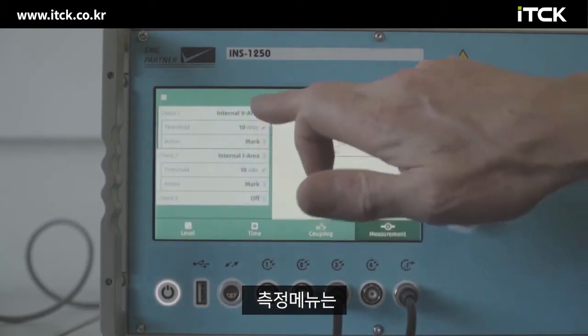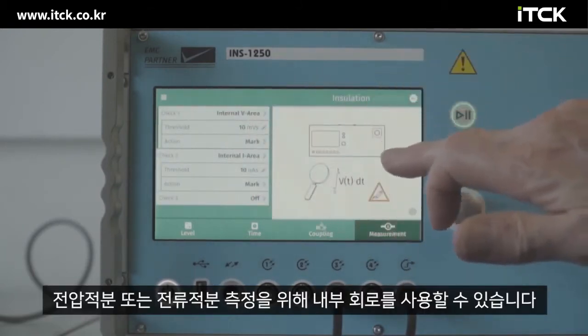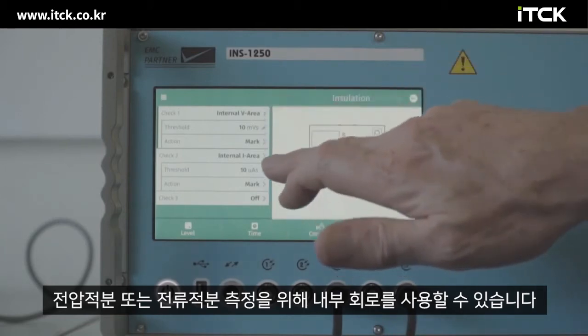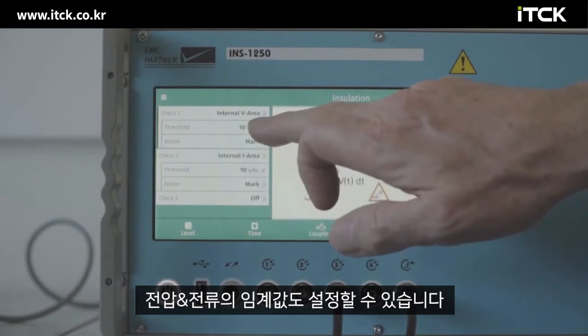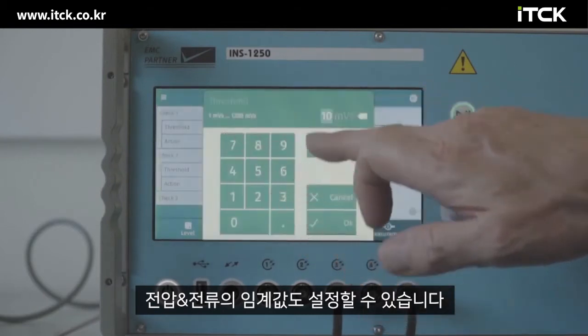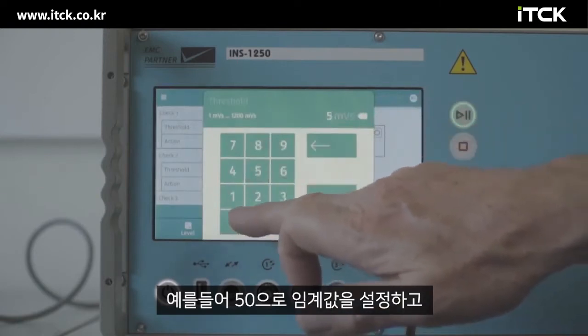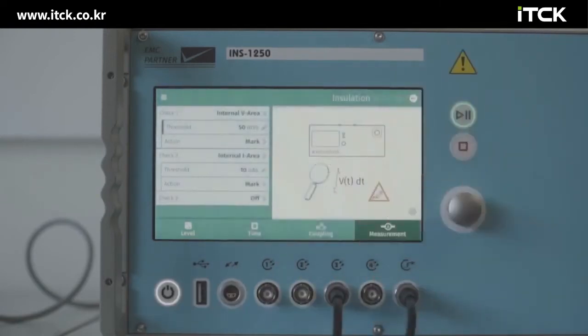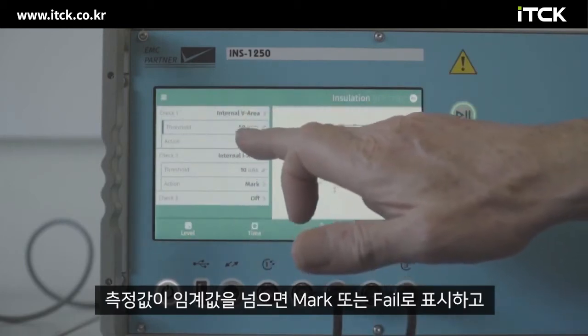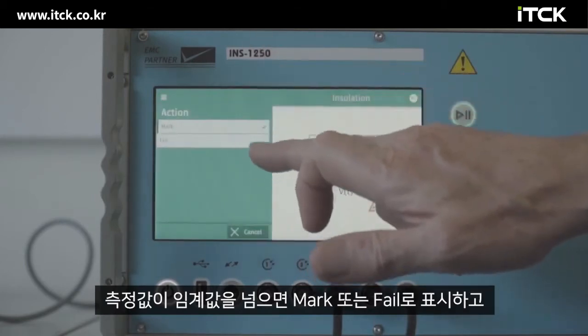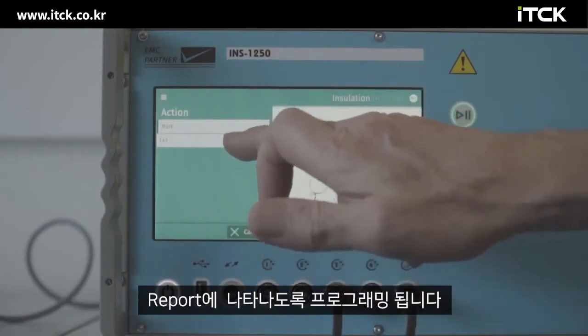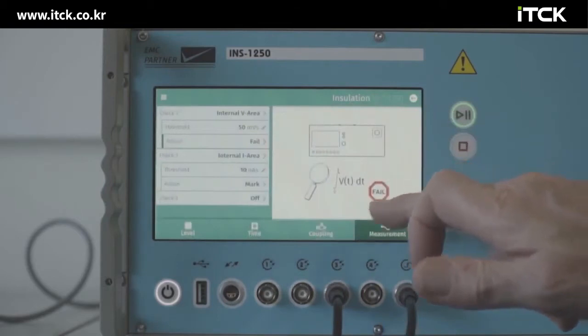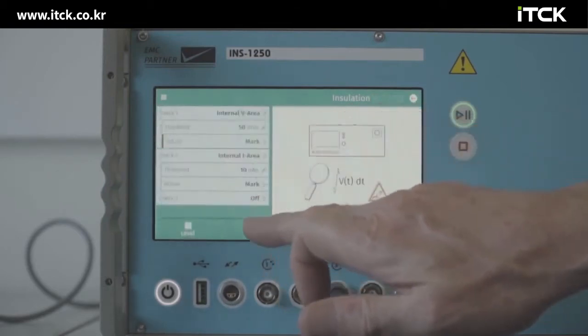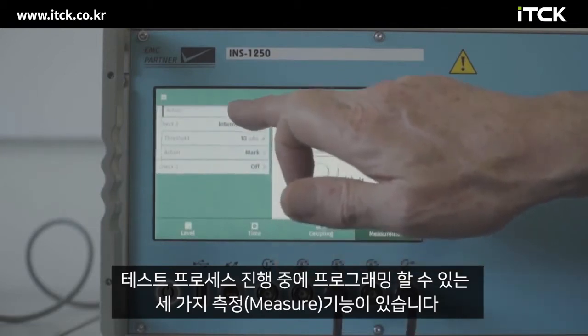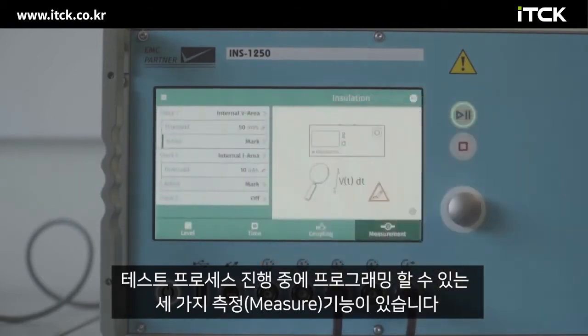Measurements within the generator. We can use the internal circuitry to measure the voltage integral or the current integral. We can set thresholds on those. So if we set the threshold, for example, to 50 in this case, and then an action can be programmed when the threshold is exceeded, either mark or fail. Back to mark. We have 3 check functions that can be programmed during the test process.